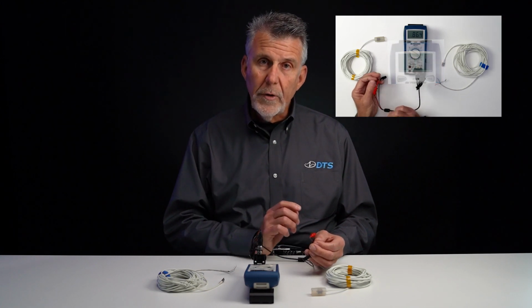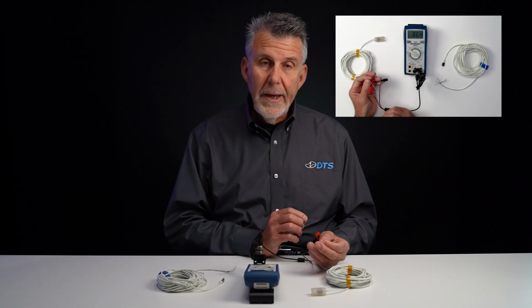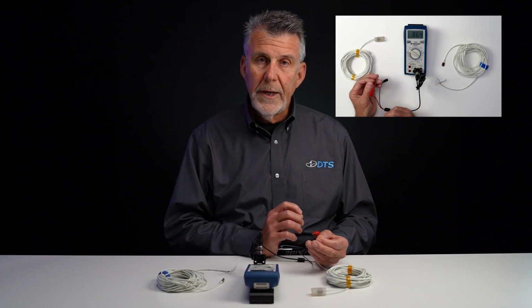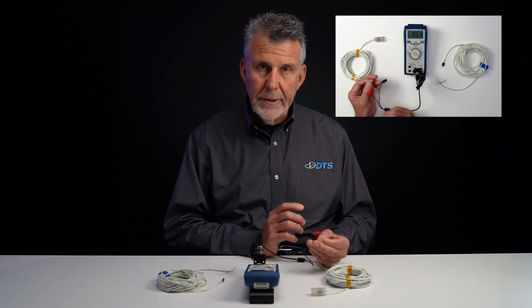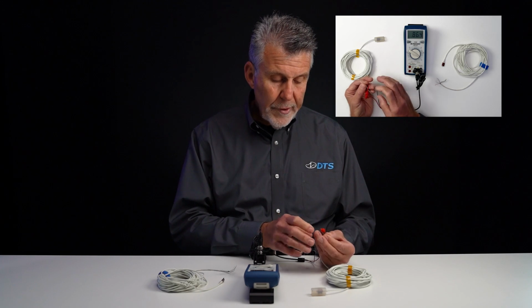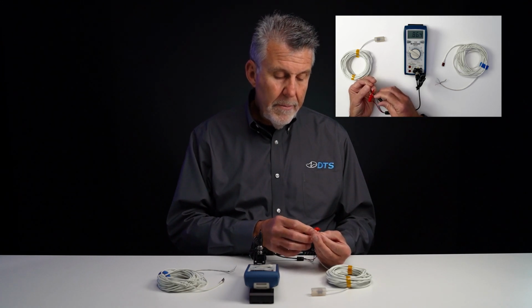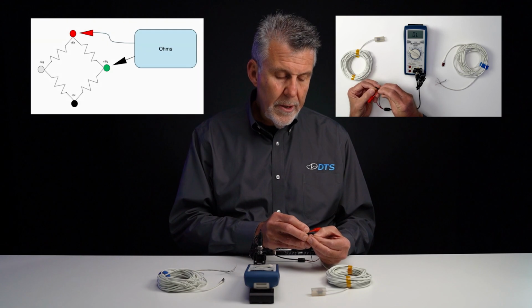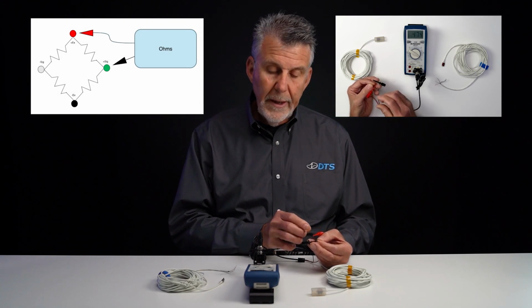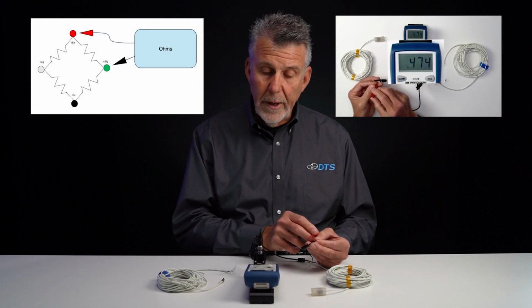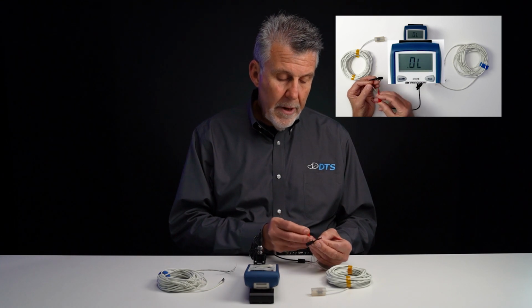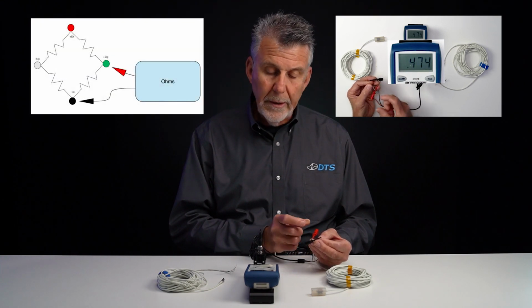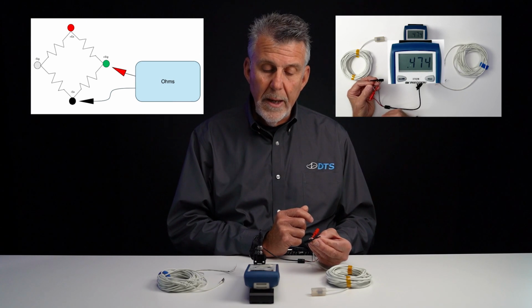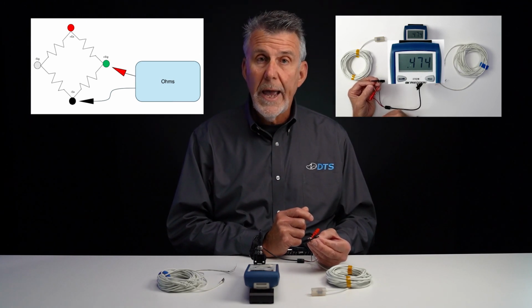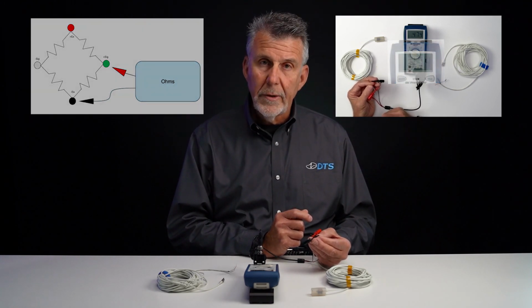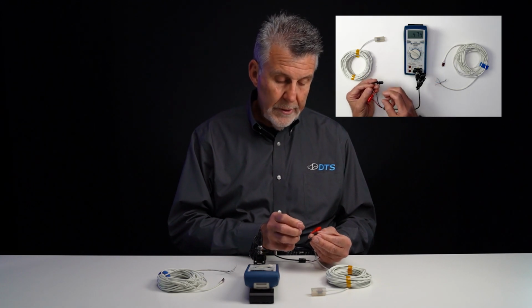Now, one of the things I want to try to do with my measurements here is to isolate whether or not there's an inconsistency or an imbalance in the sensor bridge. And so the first thing I'm going to do is measure between the plus excitation and the plus signal and see what I get. And I see 474 ohms. And then I'm going to make the same measurement between the plus signal and the minus excitation, and I get 474 ohms again. That means that the plus signal side of the bridge is balanced.